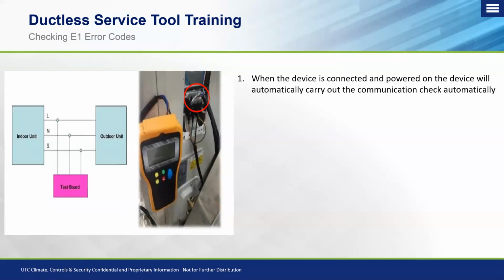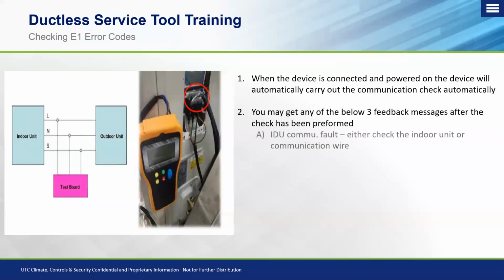The device will immediately start carrying out a communication check for the system. So if you have an E1 code, you shut the power off, plug this onto the bus bar, and power the tool on. After turning the system on, it starts getting and receiving different communication situations. So you'll get any of the 3 feedback messages after the check has been performed.